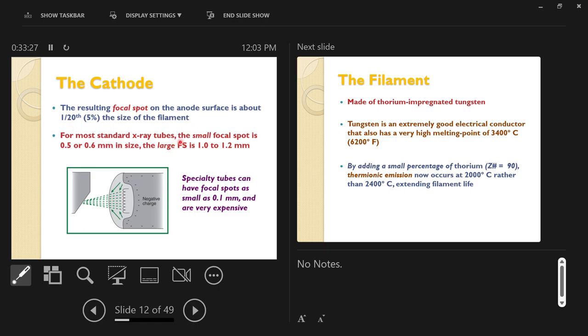Standard x-ray tube small focal spots are around 0.5 to 0.6 millimeters; large focal spots are about 1.0 to 1.2 millimeters — a tiny square spot from which all x-rays originate. A smaller focal spot gives more detail, like a single flashlight. A larger focal spot gives less detail but much more x-ray output, like having all the lights in the room on.